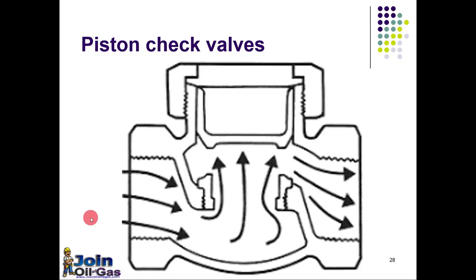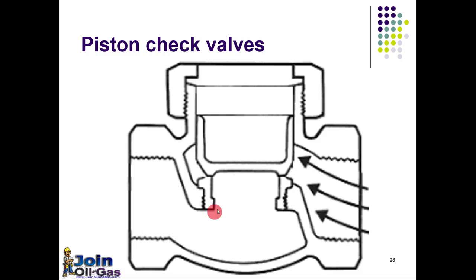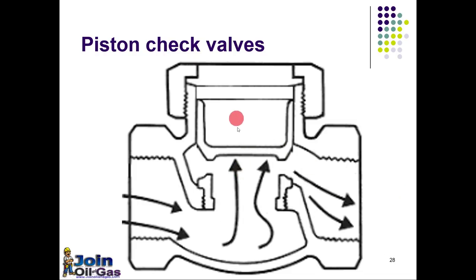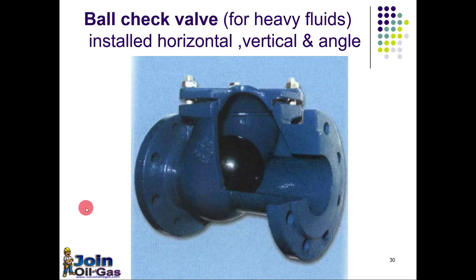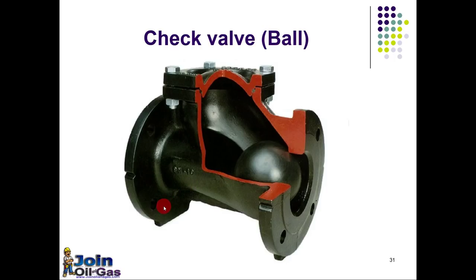This is the animation of the piston check valve — the piston is lifted and there is flow; whenever the flow tries to reverse, the piston closes. Here you can also see the ball check valve, mostly used for heavy fluids and installed horizontally, vertically, or at an angle. Inside there is one ball: when the liquid flows forward the ball is lifted up and there is flow; whenever the flow tries to reverse, this ball settles down and stops the reverse flow.